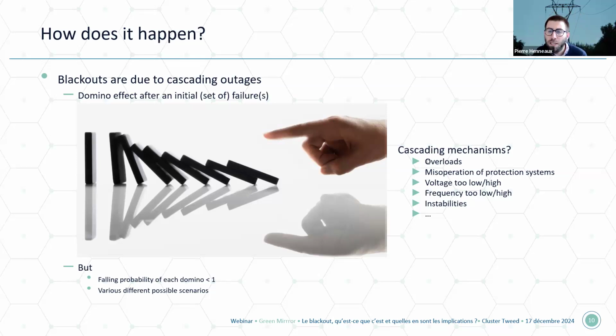The first mechanism that we see in Italy is overloads, successive overloads. But we can also have misoperation of protection systems, which can explain why sometimes a first fault can degenerate into an N-2 event, so the simultaneous loss of two elements following a single fault. We can have issues with voltage too low or too high, the frequency too low or too high, as we saw in Italy, where the frequency decrease led to the disconnection of generating units. We can also have angular instabilities. So we have various cascading mechanisms that will lead to the successive falling of elements in the power system.